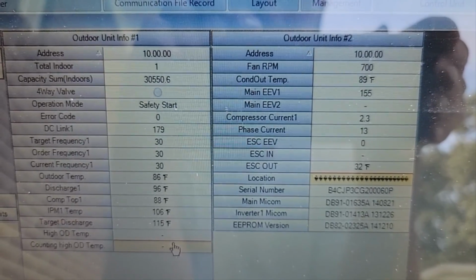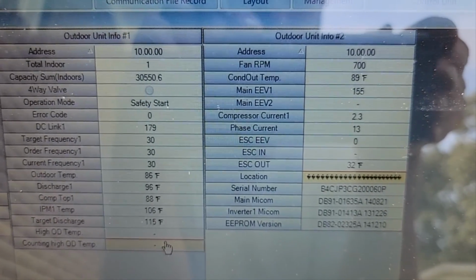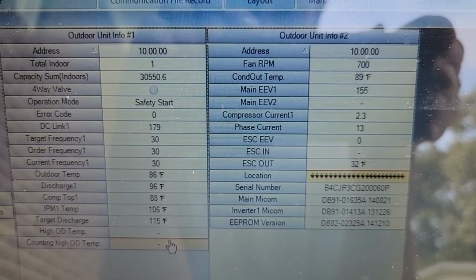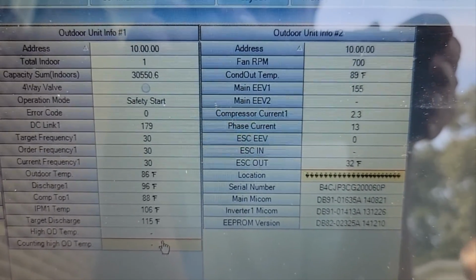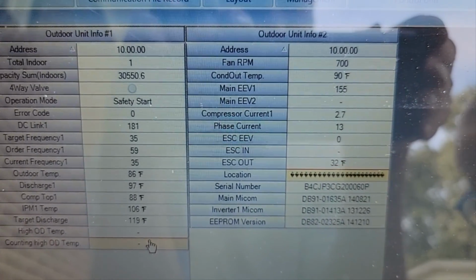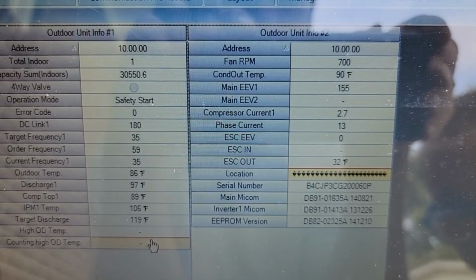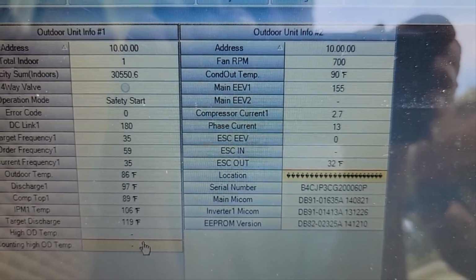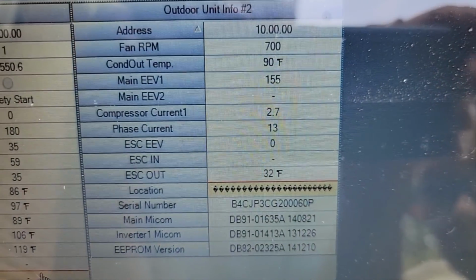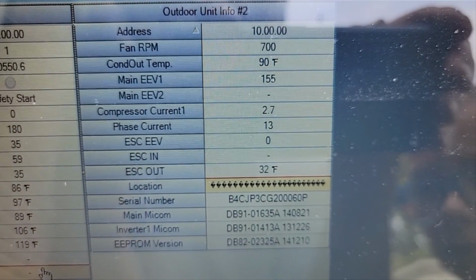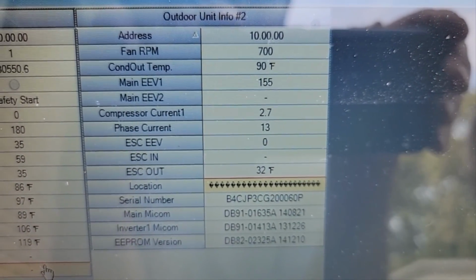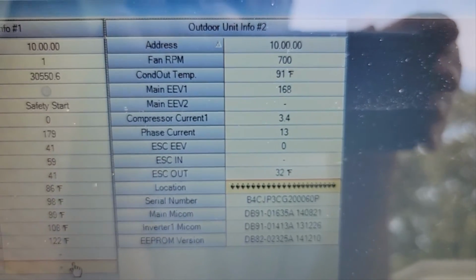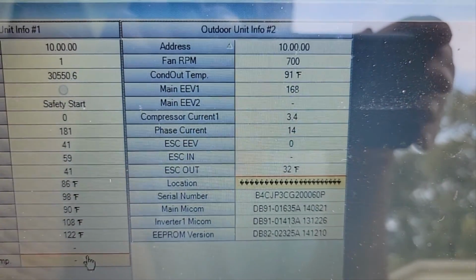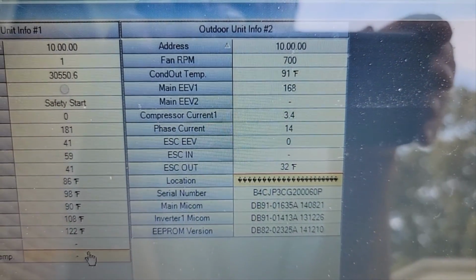Love this tool. Outdoor temperature is 86, discharge 96, compressor top 88, target discharge is 115... 119. EEV is 155. We should see a noticeable difference when we fix this equipment. EEV is 168.